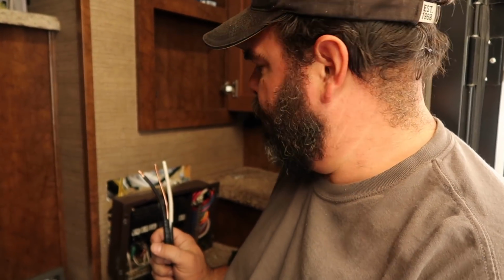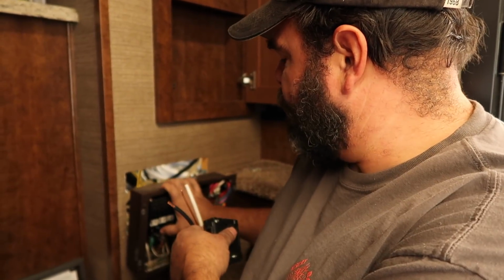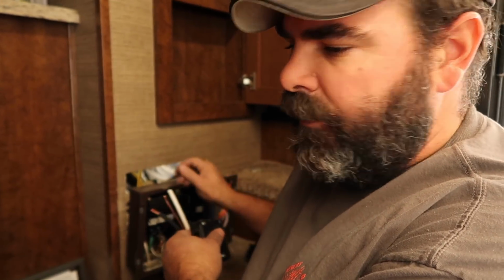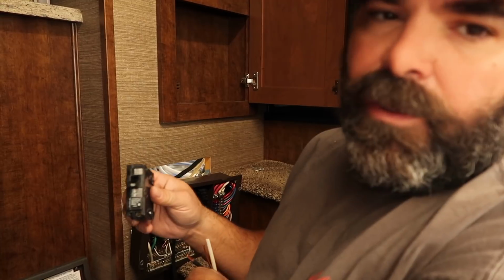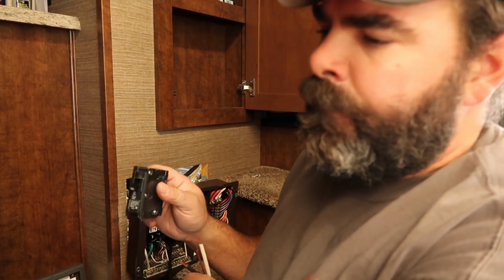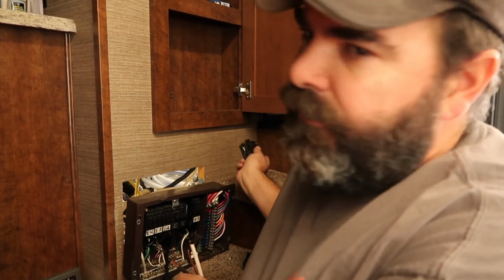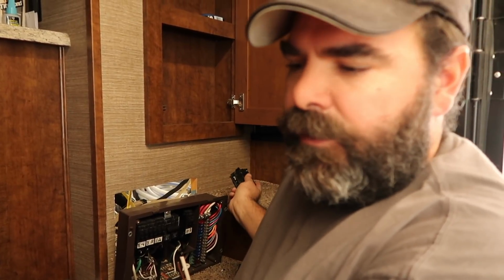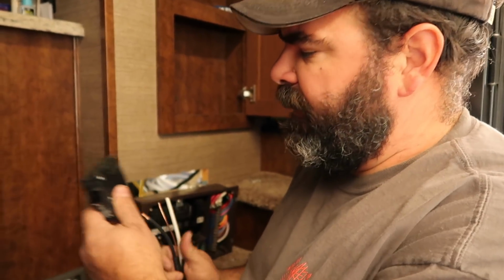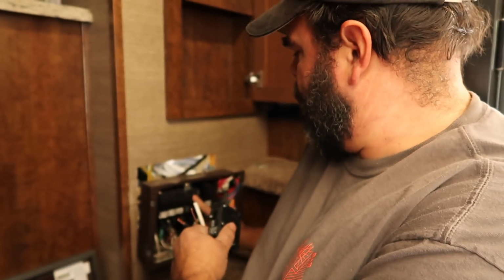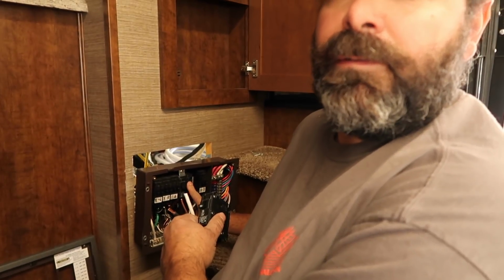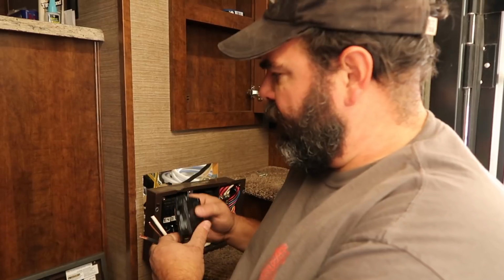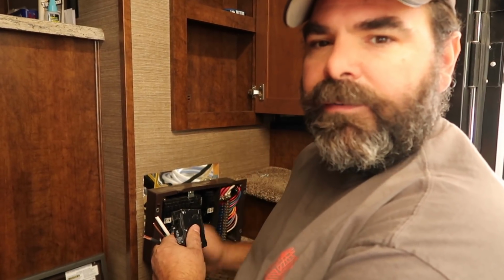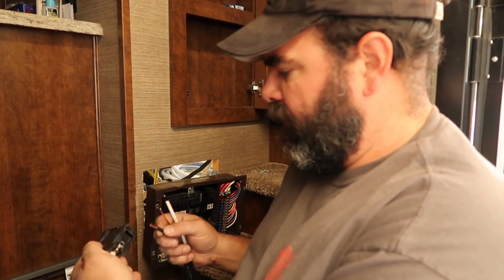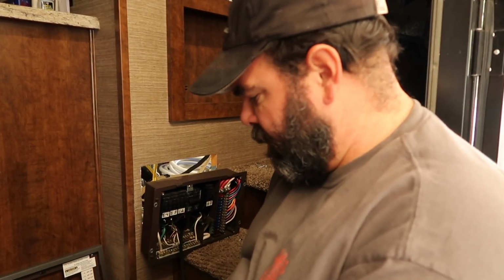Alright, so I've got the inverter feed wire fed from my original circuit breaker box to the inverter. I'm going to feed that or supply that with a 50 amp breaker. There's a 60 amp transfer switch in the inverter, but I'm only going to send it 50 amps because that's what my box is rated at here. So I'm using a 50 amp breaker here and a 50 amp breaker in the sub panel. Just working on getting this stuff all hooked in right now.